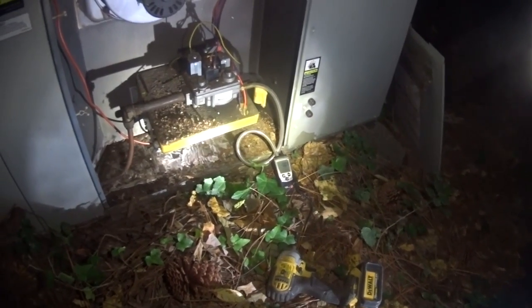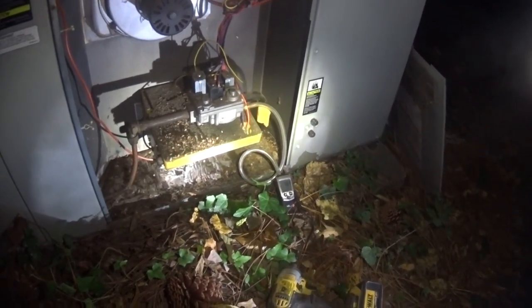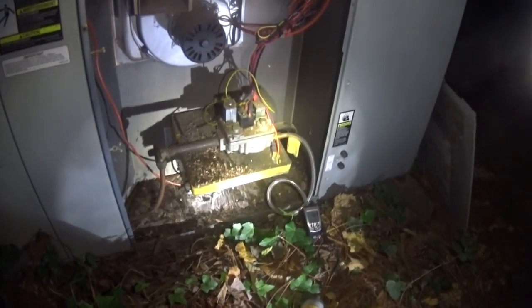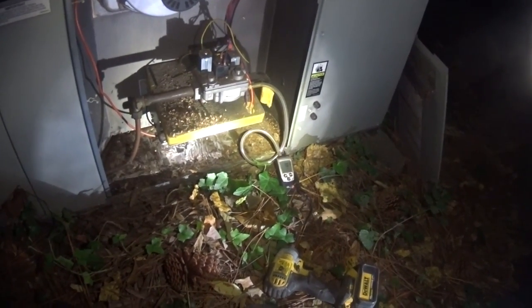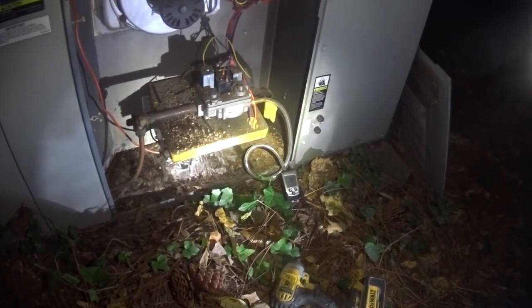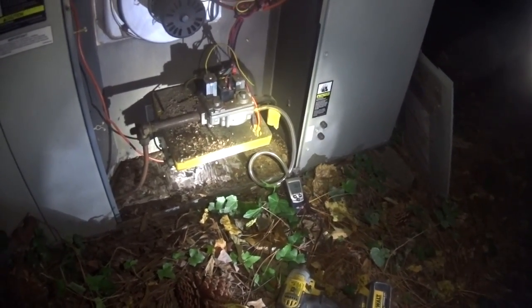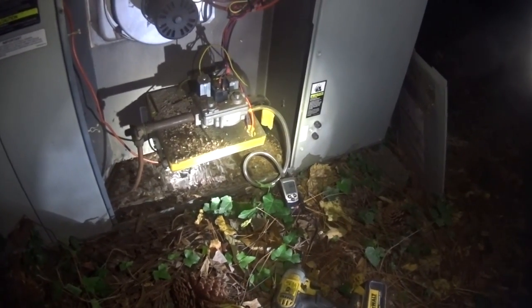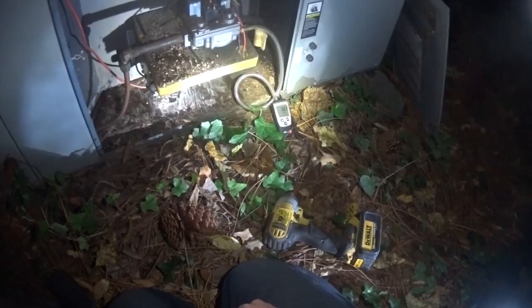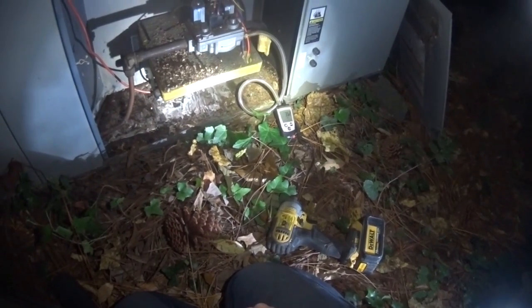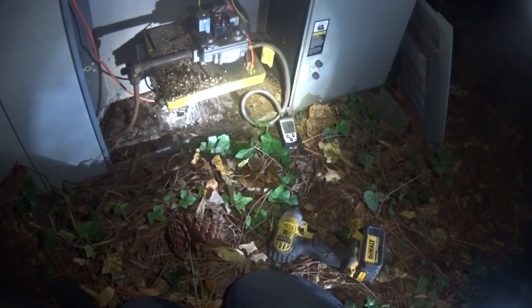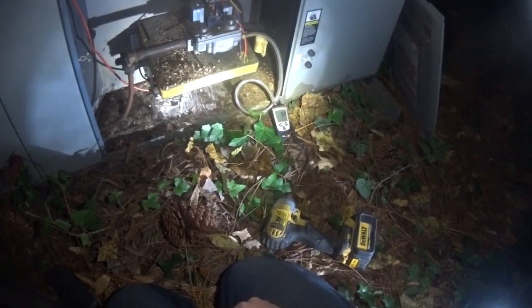Didn't happen to notice what the gas pressure was. I would imagine that our flame sensor is dirty, or the burners are dirty, like the one we looked at earlier, where the flame is not crossing. We'll let it try one more time and see if we can pay attention to the gas pressure. 3.5, 3.6, 3.5, 3.6, down to 3.3.